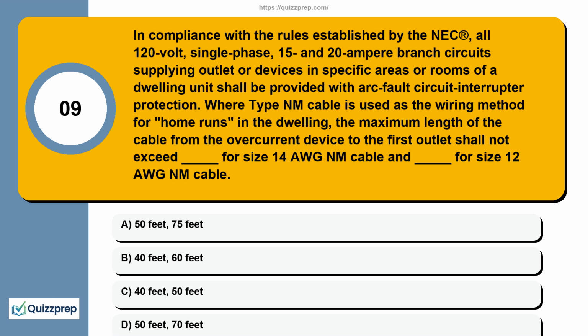Question 9. In compliance with the rules established by the NEC, all 120-volt, single-phase, 15 and 20 ampere branch circuits supplying outlets or devices in specific areas or rooms of a dwelling unit shall be provided with arc fault circuit interrupter protection. Where type NM cable is used as the wiring method for home runs in the dwelling, the maximum length of the cable from the overcurrent device to the first outlet shall not exceed __________ for size 14 AWG NM cable and __________ for size 12 AWG NM cable. 50 feet, 75 feet; 40 feet, 60 feet; 40 feet, 50 feet; 50 feet, 70 feet.